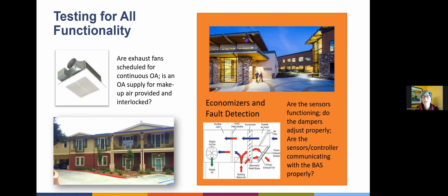A classic example of why commissioning is worth it has to do with economizers. If you're not that familiar with economizers, what we mean is that on your heating and cooling system, you're able to introduce a lot of outside air into the air handler that goes into the building. When the temperature is right and the air is cool and you're calling for air conditioning, you've got free cool air, free air conditioning. You just run your fan, but you allow the economizer to open the dampers and pull in a lot of outside air into the space, and not have to keep recooling the recycled air or supercooling really hot incoming air.